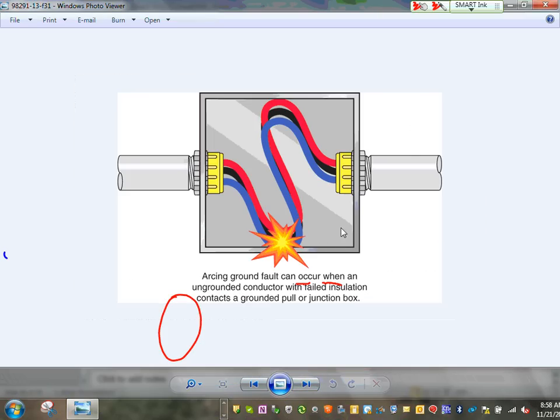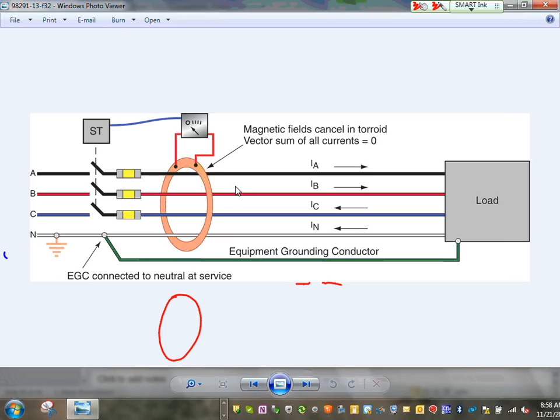The reason again why we bond is because accidents happen and energized conductors could get in direct contact with metal objects and become energized. The way they design the ground fault, guys, this is a ground fault. They have a sensor either around all the conductors or one sensor around each conductor. They sense the difference in the current coming in, coming out, and if it's substantial, it will trip the disconnect or the circuit breakers on a ground fault.